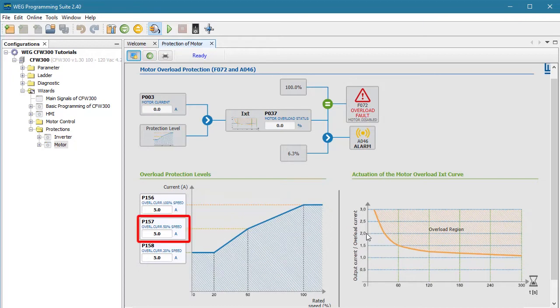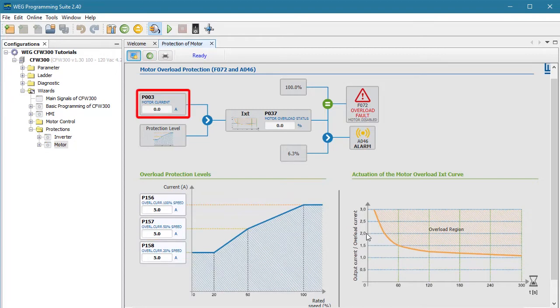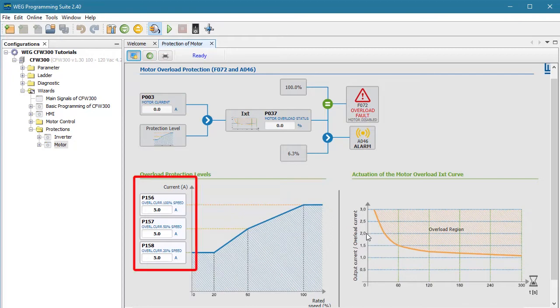Repeat that for the 50% speed and again for 20% speed. Measure the actual current under normal loads at those speeds, add about 10%, and put the result in these parameters. That would give you an overload protection curve that represents your normal system loading.